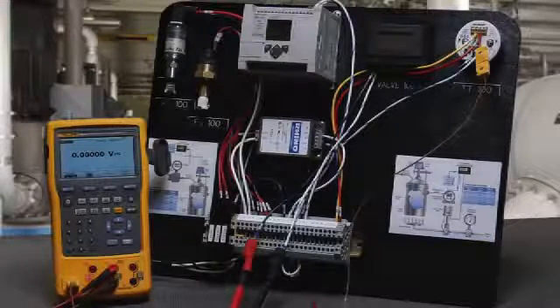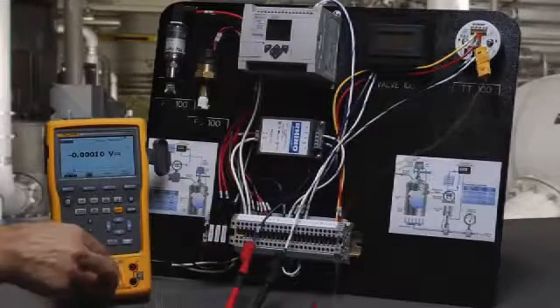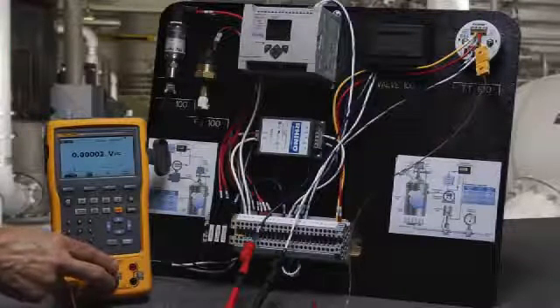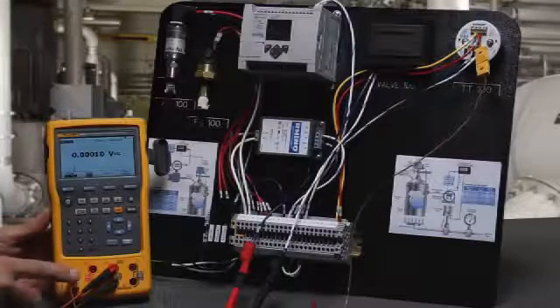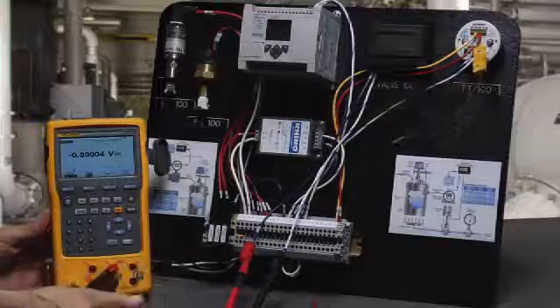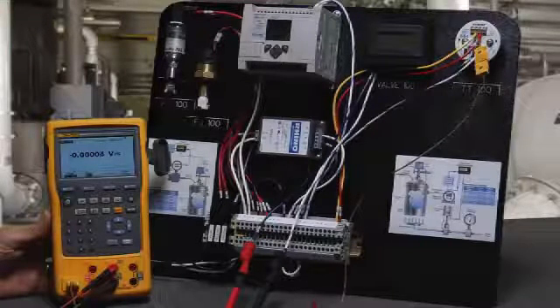We're going to measure the milliamp signal of the transmitter on the input of the 754 and we're going to power it with a 24 volt loop power supply internal. We're going to source or simulate a temperature signal to the input of the transmitter while simultaneously measuring the milliamp output and calculating error percent of span.